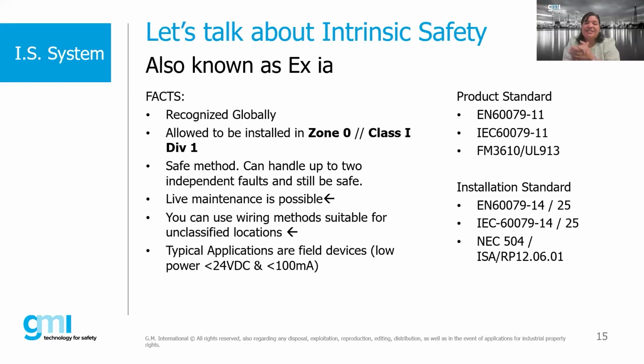Thank you, yes absolutely. So intrinsic safety, as Bob was mentioning, is going to minimize the amount of energy going into the field. You will not be able to create heat or energy enough to react with an explosive atmosphere. But I want to highlight a few things about what the intrinsic safety protection method also provides to all the engineers out there doing installations. One fact about intrinsic safety is that it's globally recognized. So if you want to standardize on a way of installation, intrinsic safety is one of those protection methods that is extremely similar, not the same, but extremely similar between ATEX, IECEx, and North America. So that will be an advantage.